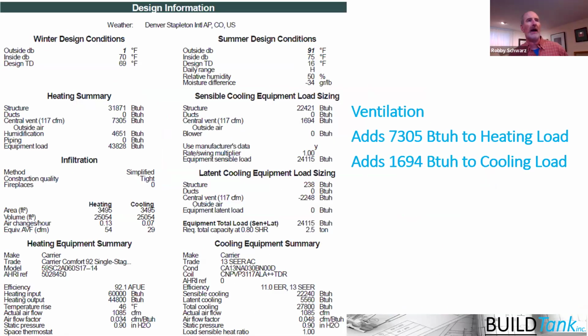So how does this relate to the Manual J? Ventilation adds, in this case, 7,300 BTU per hour to the heating load and almost 1,700 BTU per hour to the cooling load of our houses. We would look in the heating summary, the design information page of the reports, and we would look there. In this case, it's a central vent strategy. It's pushing 117 CFM of air, and it adds that much load to the house.